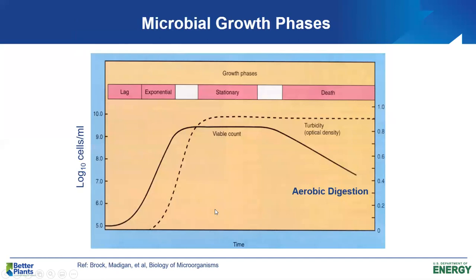Looking at our microbial growth curve, we have several growth phases: lag, exponential growth, stationary growth, and then the death or endogenous phase. When we operate activated sludge, we normally operate somewhere in the stationary phase into the death or endogenous phase. So when the sludge comes out, it's partially oxidized but still has some biomass that needs digestion. In aerobic digestion, we push it further into endogenous decay and try to fairly completely oxidize that biomass to CO2, water, ammonia, and other end products.